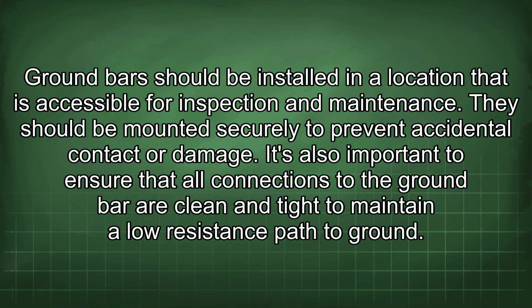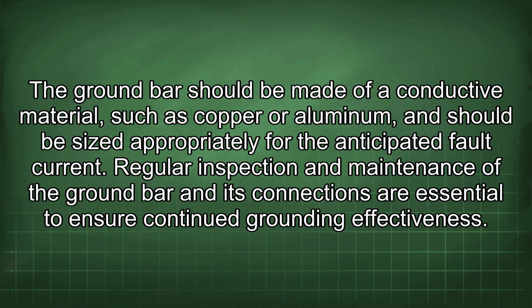resistance path to ground. The ground bar should be made of a conductive material, such as copper or aluminum, and should be sized appropriately for the anticipated fault current. Regular inspection and maintenance of the ground bar and its connections are essential to ensure continued grounding effectiveness.